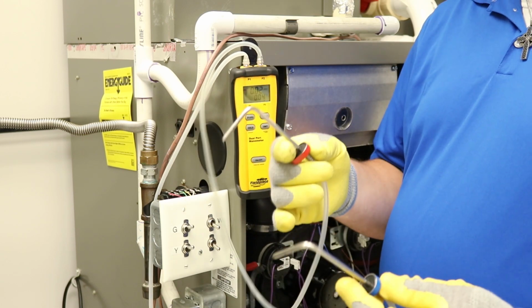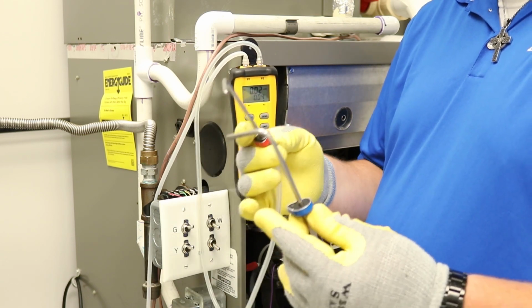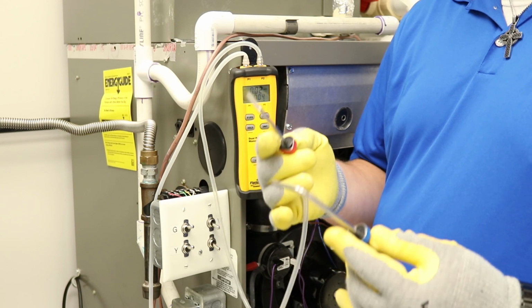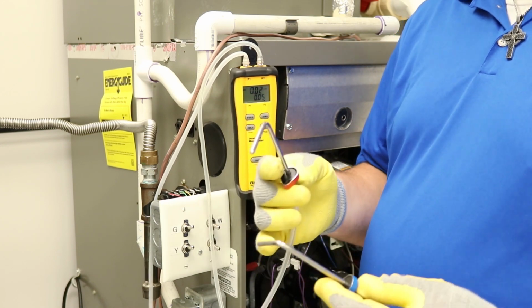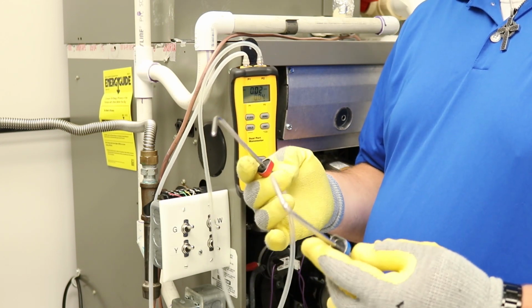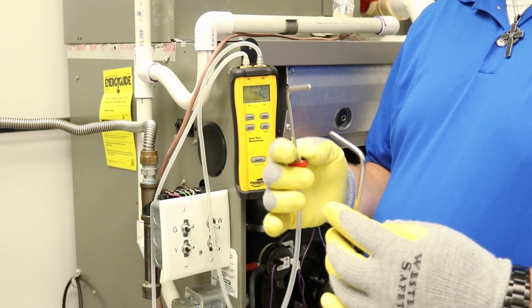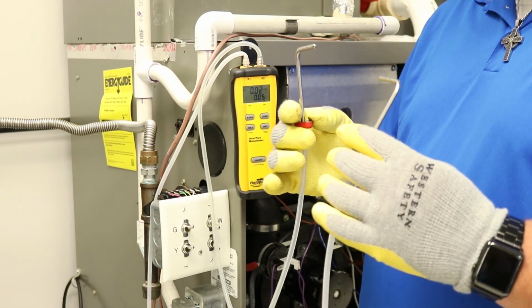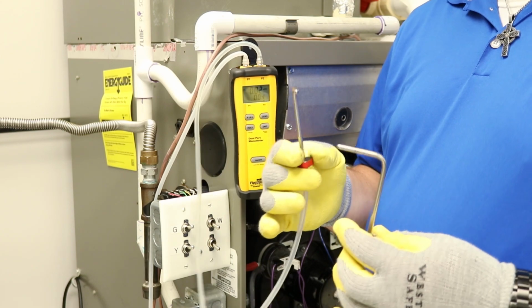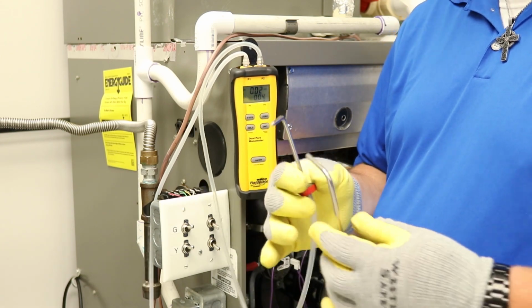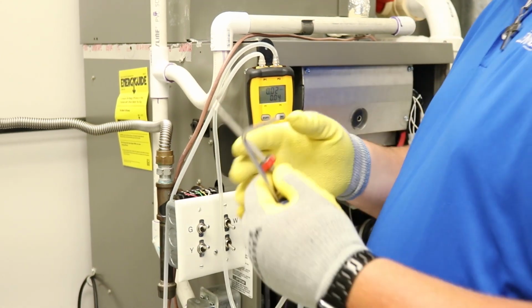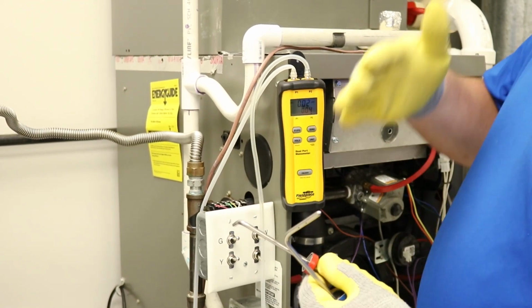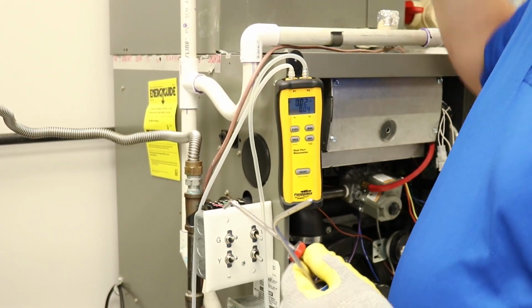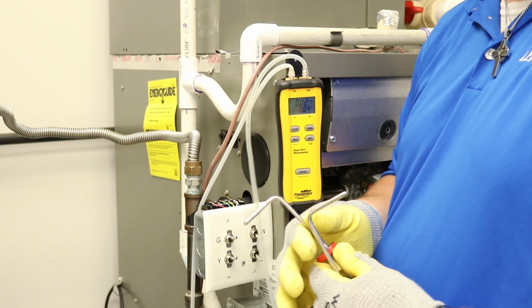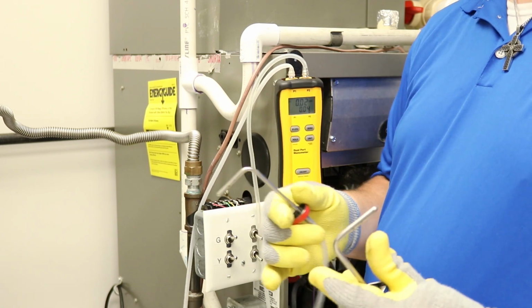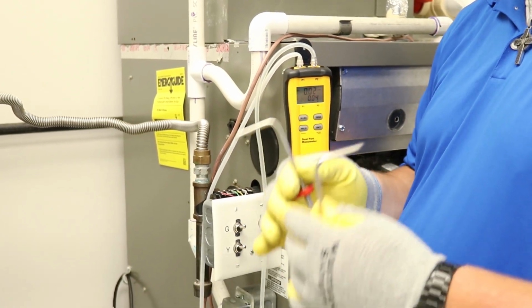The next thing that's really important when you're talking about the placement of these probes is making sure that you're keeping it inside the box. Again, that's something that is going to be paramount in determining that you have the right static pressure for the system. A lot of technicians will want to install these to where one's on the opposite side of the evaporator coil and one's on the other side of the air filter. That's not the proper way to check static pressure. You want to keep it inside the box.